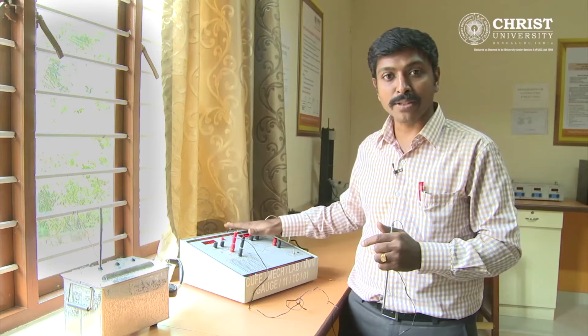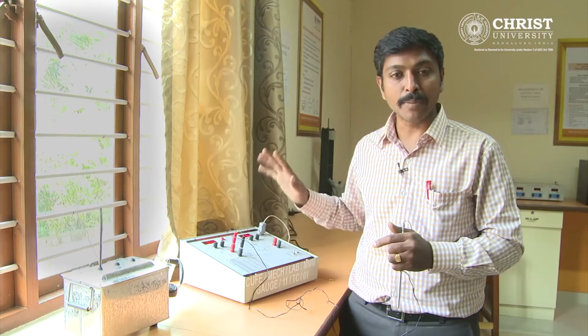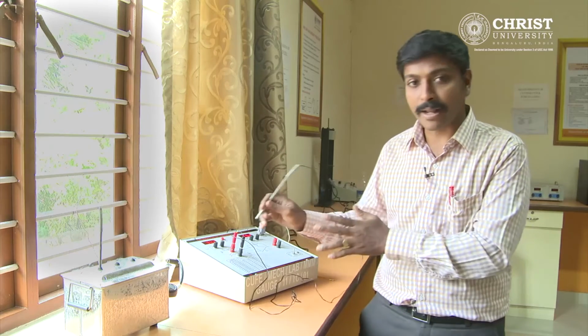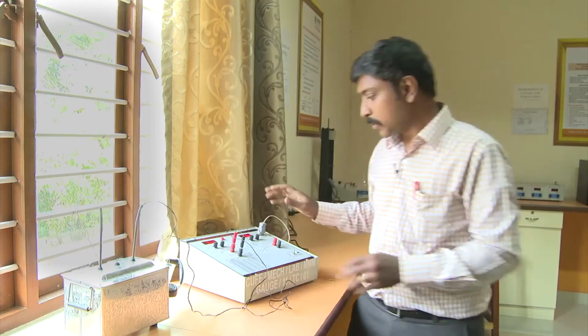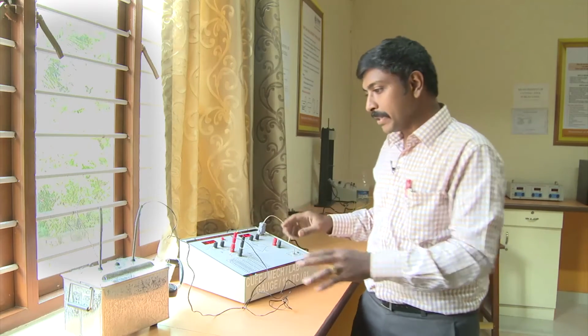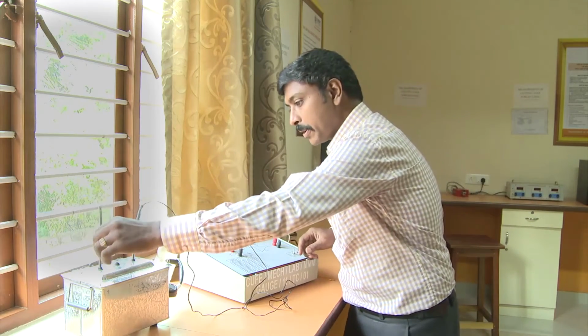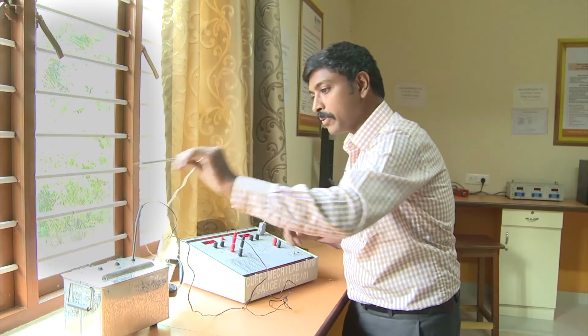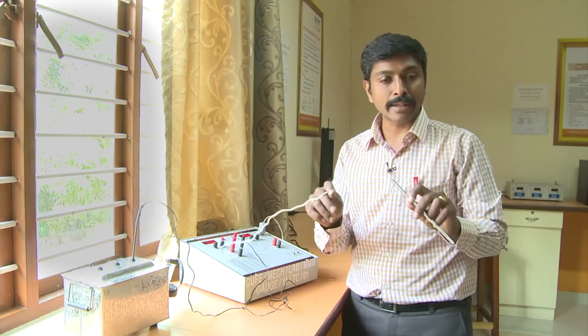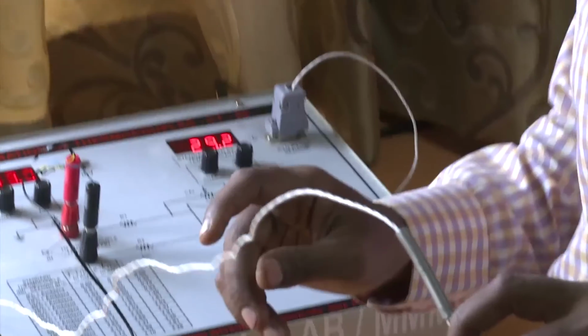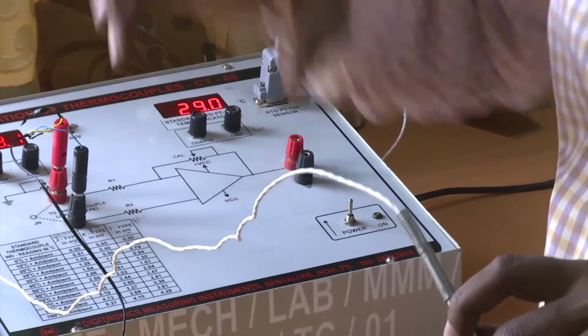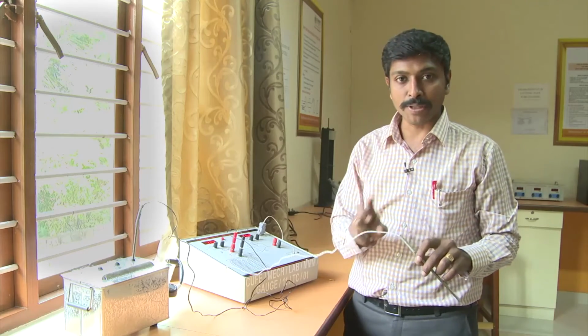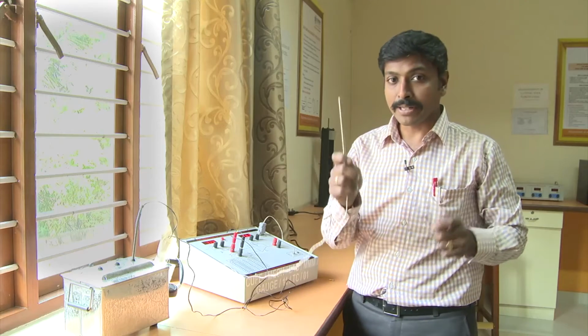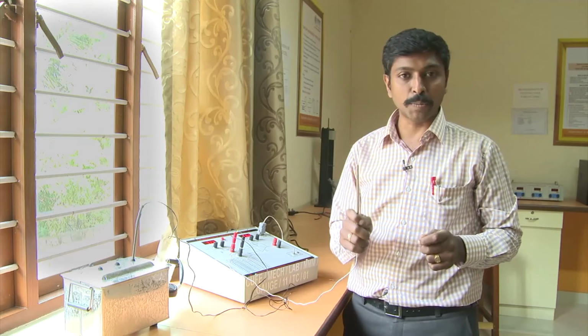Then that becomes the basis for creating your calibration of thermocouple. Now we will go inside how to measure with that equipment. So first, when you see this kit, we have two probes coming from the two sides. One is your RTD, resistance temperature detector. I told you that calibration is a process of comparing two equipments. One equipment, I have to treat as a standard equipment or ideal equipment.